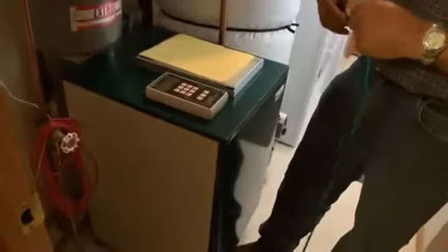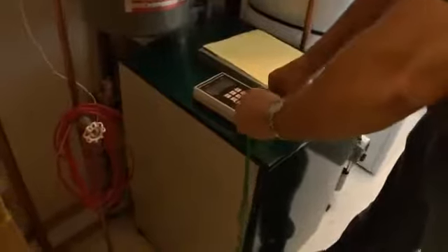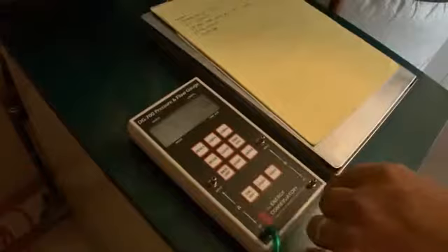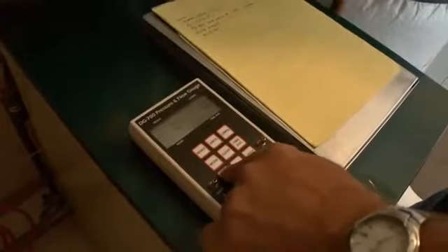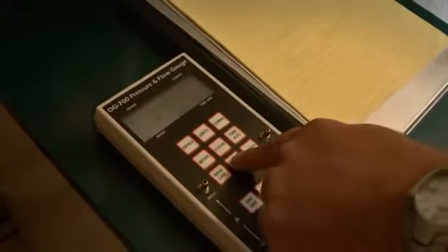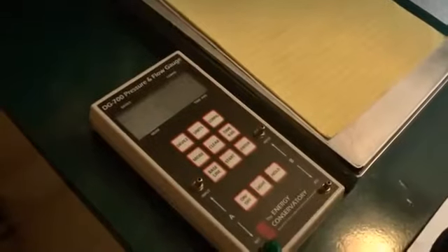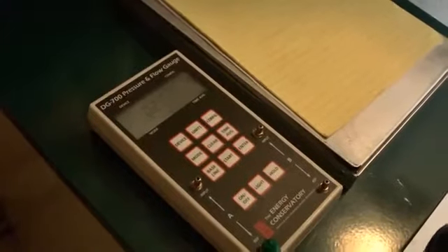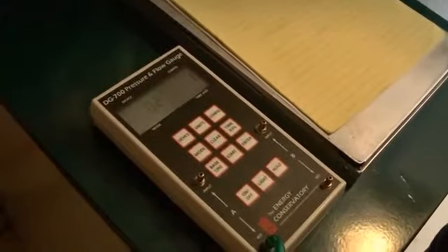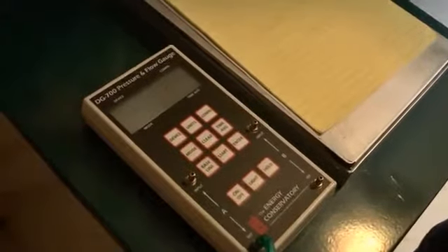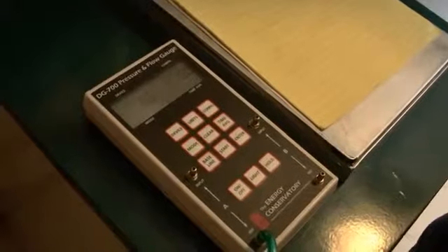So we'll turn on our DG700. We're going to read our pressure with respect to outside. Okay, we need to get baseline pressure. So we're on pressure. We're going to get baseline pressure. We'll start the calculation. Now this thing will go through a process and average out the baseline pressure. We'll let it go for 30 seconds or so. We select enter, and now everything's with respect to baseline pressure.